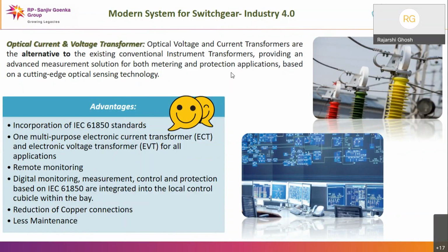Presently, optical fiber CTPT, etc. are available in the market, which are very easy to handle and can be used for all applications with much simpler connections. In our case, we have a backup core, a main protection, main 1, main 2, all these things. Many cores are required, but with optical fiber the same core can be used for different applications. So the equipment also becomes smaller in size, lighter in weight, and one multi-purpose CTPT can be used.